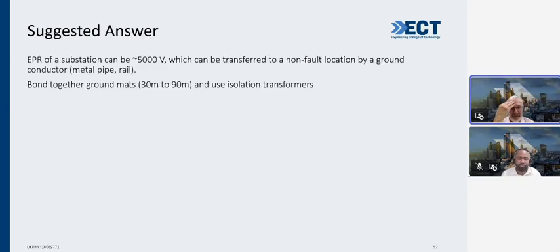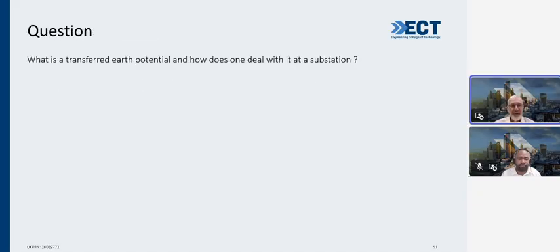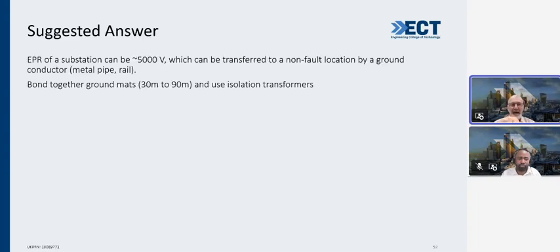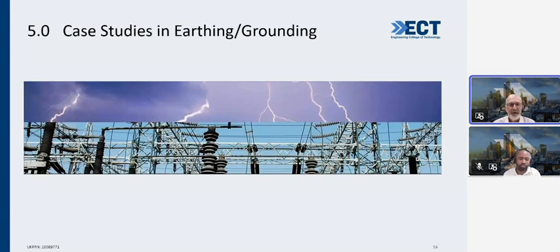So you're right. Really, with transfer potential - earth potential, EPR is earth potential rise - it can be transferred to a non-fault location if you've got a metal pipe going through the site. So you obviously use ground mats and isolation transformers, otherwise you'll find you're connecting to remote sites.